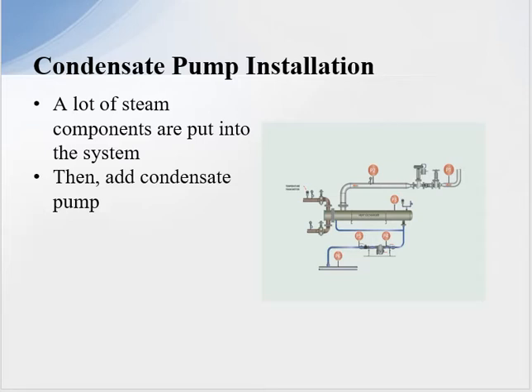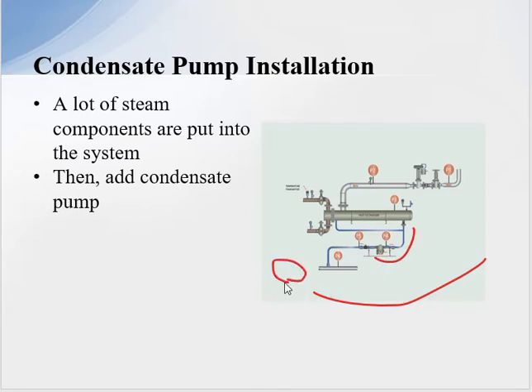In condensate pump installations, a lot of components are put into the system and then we add a condensate pump. This is a common application — we have a shell and tube heat exchanger coming down through a steam trap and then into a condensate return system. The question is: do we need a condensate pump there to get the condensate back? It depends on a number of variables, and we have to look at it as a system, not just a single component.